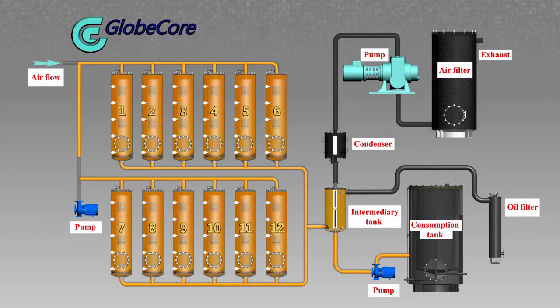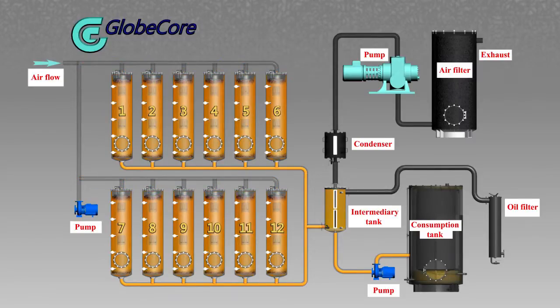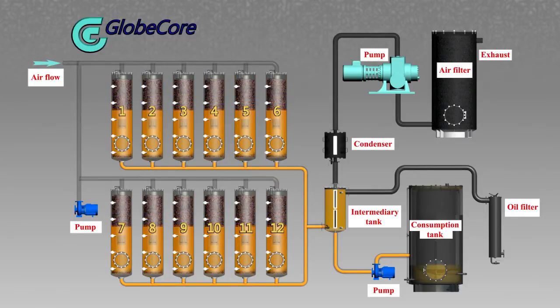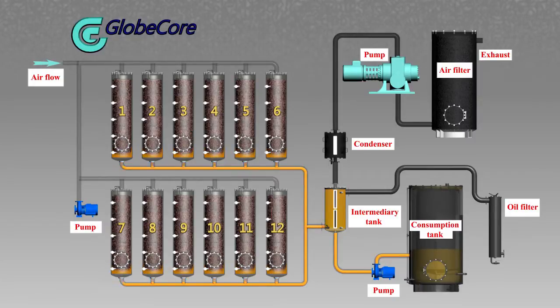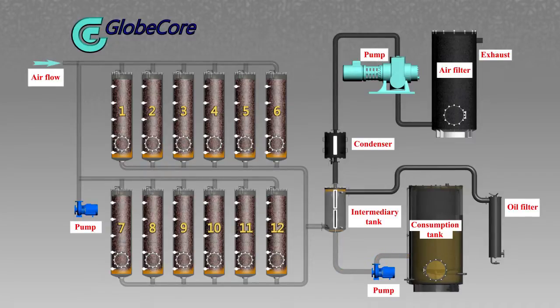Reactivation process runs as follows. The output pump drains the oil from sorbent columns and puts it into the buffer tank. After the columns are completely drained, the vacuum pump starts. The vacuum pump creates air flow for the columns. Then the sorbent surface heater switches on. At this time, sorbent reactivation starts and absorbed oil decomposition products are extracted.